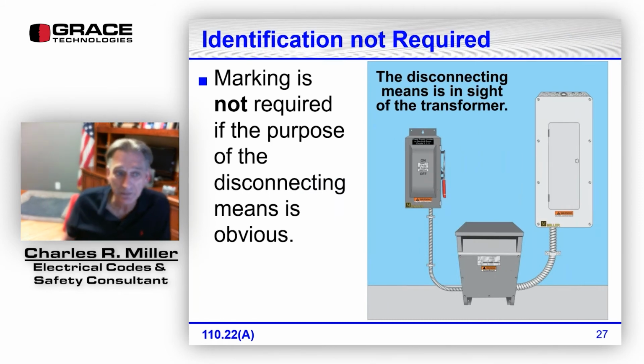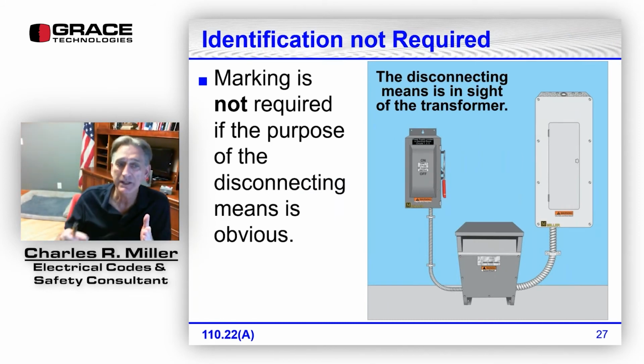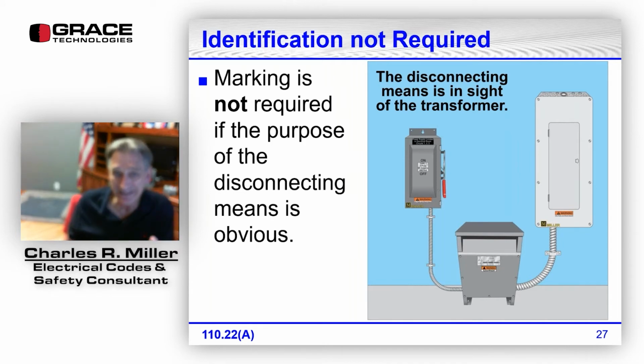All right, marking is not required with that disconnecting means because the purpose is evident. It's obvious. So the disconnecting means is within sight of that transformer. Yes, it can be marked, but it does not have to be marked because its purpose is evident where it's going to.